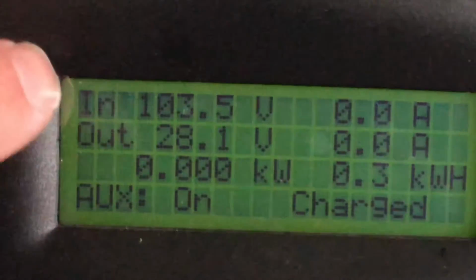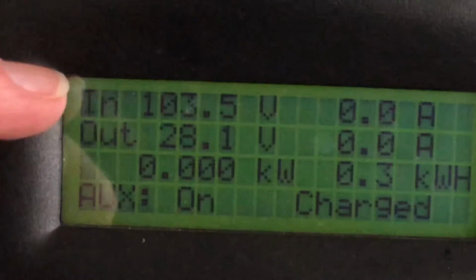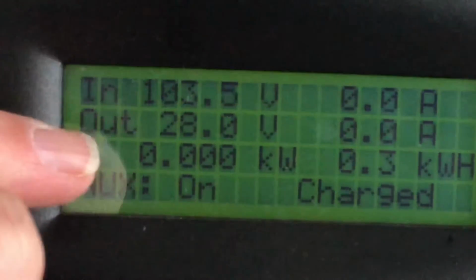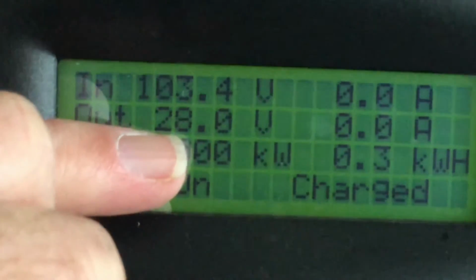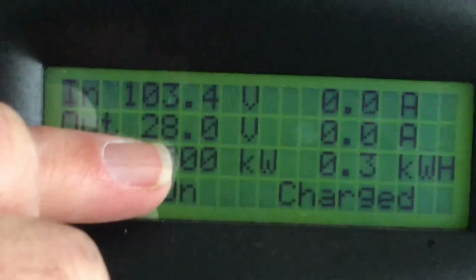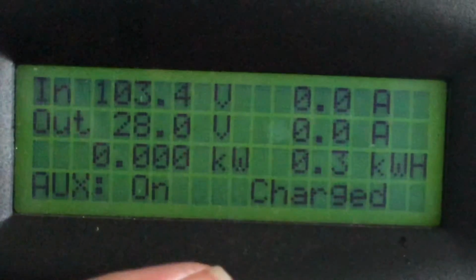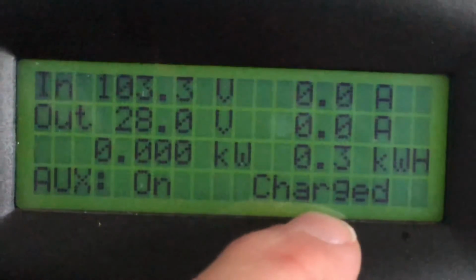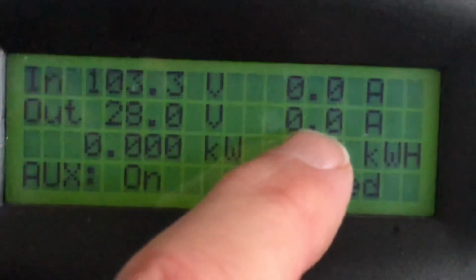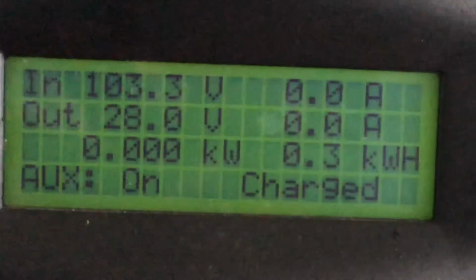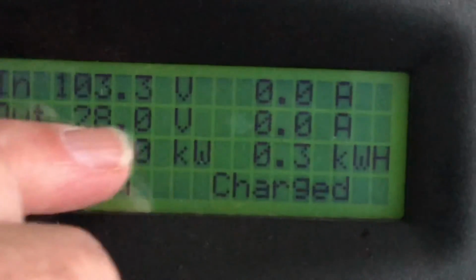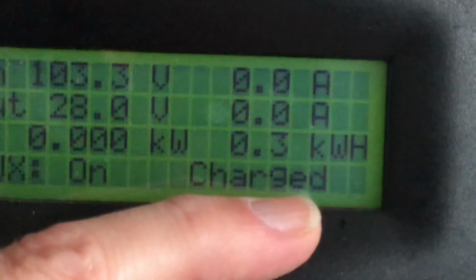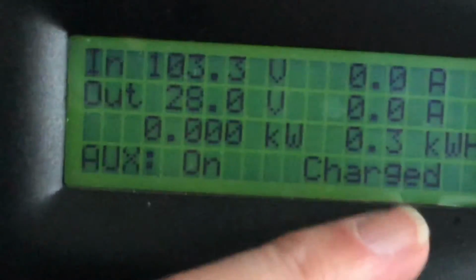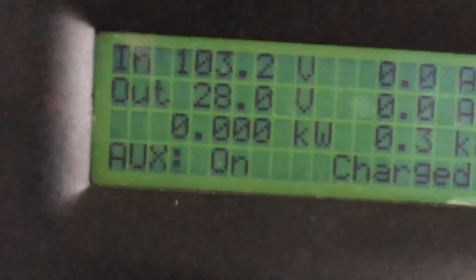The data on the solar screen, the top line is the panel voltage coming in and how much current is coming in from the panels. The out is the battery voltage, that's the actual battery voltage. That should not get above 28 volts. And that's how much current is going into the battery from this charge controller. The charged says that it's fully charged and it's finished charging. That's why we see nothing coming in. As soon as load comes on the house, the solar panels will start charging again to support that load so the battery doesn't discharge. That's if it's during the day.